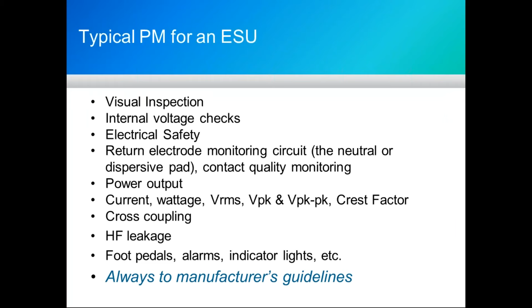For a typical PM, I'm sure all of you have done the many PMs in the past. You do the visual inspection, and you go through the list: electrical safety, the high frequency, the foot pedals, but you always refer to the manufacturer's guidelines. For the Covidien FX, in the service manual, page 513 is where it starts. You'll notice it says, check the foot pad. In my shop, it was always a running joke that the casters are good.